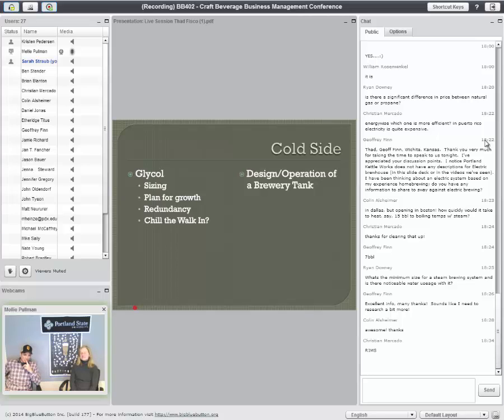So a fermentation vessel: conical bottom, upright sides, wrapped with a jacket around the outside. In that jacketing, you're pumping glycol through. In fermentation, you're going to be maintaining something slightly under 70 degrees, typically for your ales. And that glycol system and that tank work in unison with one another. So you've got a temperature probe, just like your thermometer at home. If the tank gets too warm, the probe is going to say, hey, you've reached 72 degrees here.